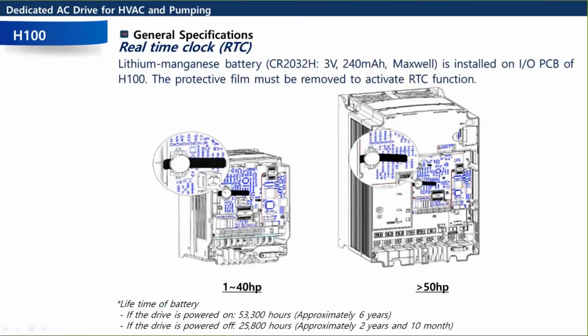The H100 is the only drive with a real-time clock, commonly called an RTC for short. So for those of you that didn't know about that, and have set up many H100 drives, the clock is actually disabled by default, so that might be why you didn't know about it. As we're showing you in this picture here, if you pop off that front cover, there's a battery. It's like one of those quarter size 2032 batteries. There's a little plastic slip behind that battery, so you remove the slip, and then the battery makes contact, and then you could set your clock. So that's the first thing you've got to do if you want to set your clock.